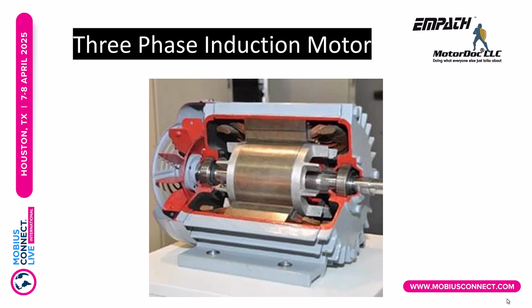So let's get into the purpose, and that is to understand what we're doing with the electric machines. So this is just a cutaway of an electric machine I took some years back from a repair shop that I worked at. And it just shows you the rotor, and there's rotor bars, and there's basically an aluminum end ring on either side of the rotor that shorts those all together. There's a stator with laminations, and those hold the coils in place, and then there's an entire frame and cage.